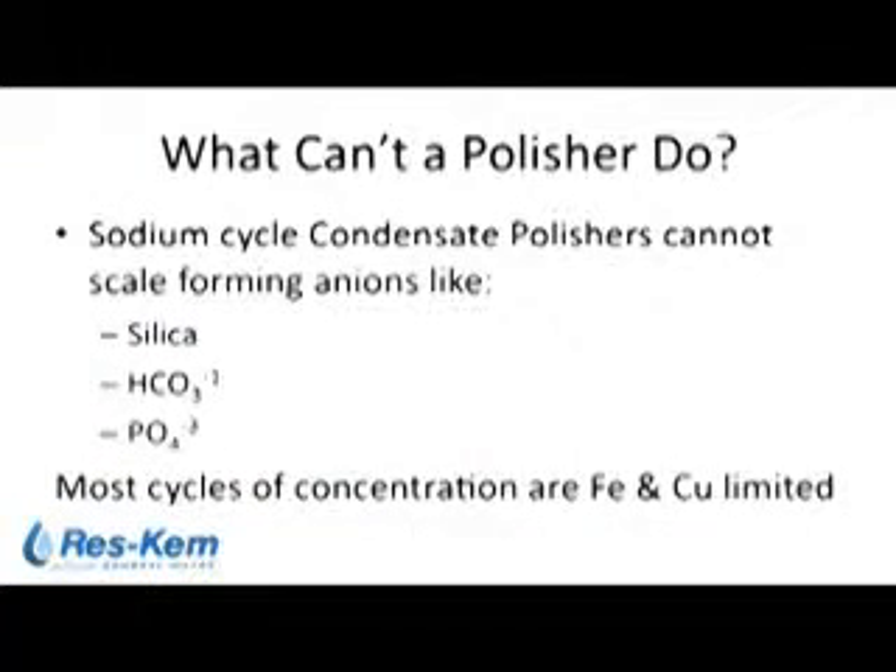Installing a polisher basically guarantees, or helps to guarantee, that on annual boiler openings there will be no surprises with deposits on your boiler tubes. What can't a polisher do? Silica — mentioned earlier in the presentation — cannot be removed by a condensate polisher simply because it's an anion constituent and the resin being used is strong acid cation. It cannot remove silica, bicarbonate, or phosphate. But most of your cycles of concentration in your boiler water are related to copper and iron in your return condensate.